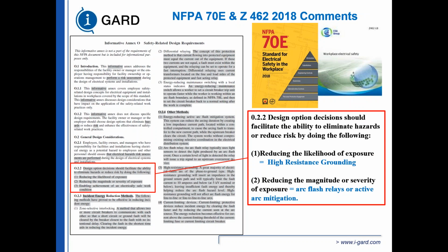So, reducing the likelihood of exposure: high resistance grounding. To reduce the magnitude or severity of the exposure, use an arc flash relay or an active arc mitigation system. With the SMART HRG system, you can do both. You can have the benefits of the high resistance grounding system and follow this here, and you can reduce the magnitude by using an arc flash relay here.